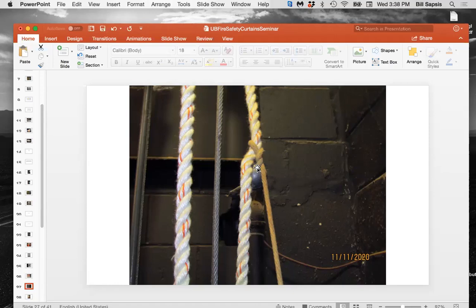When tension is released, the theory is that the line will open up a little bit, the lead ball will pull out and fall away, allowing the arbor to go up, because we've been holding the arbor back. That theory works about maybe 60% of the time. If you have this particular system, there's no prohibition to using it. You can still do it if you want. I don't think it's reliable enough to use, and I would recommend that you replace this.